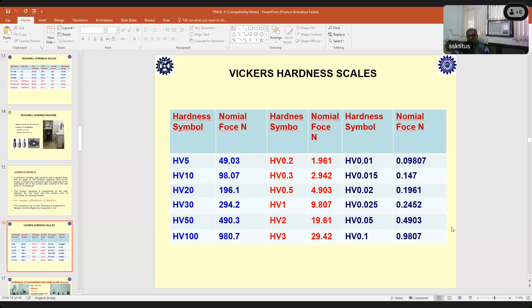So we have HV5 scale, HV10 scale, up to HV100 scale. Depending upon the requirement, you can use this scale. And these we can call micro Vickers scales: 0.2, 0.3, again it is 200 gram, 300 gram, 500 gram. Even 0.01 is also there. So HV scale is very vast, and for the micro Vickers scale, the only thing is the tolerance in the pyramid cone is different. The tip is again 136 degrees, but for the conjunction length and other things, there is a limit which the indenter has to satisfy.